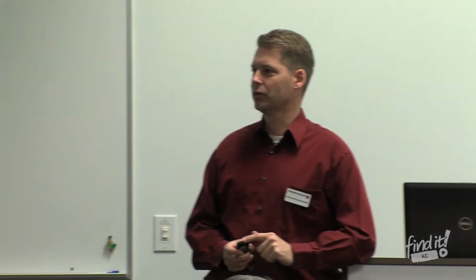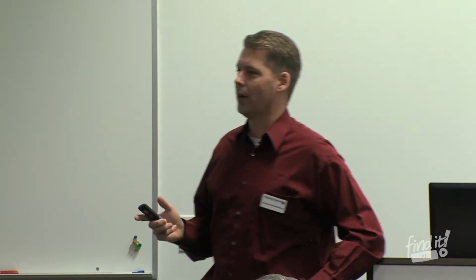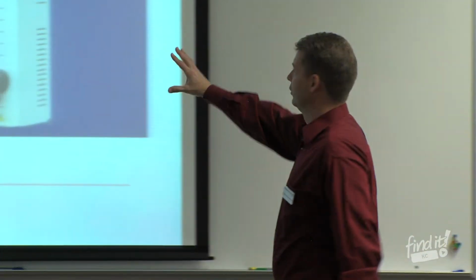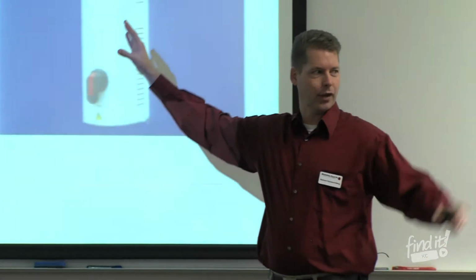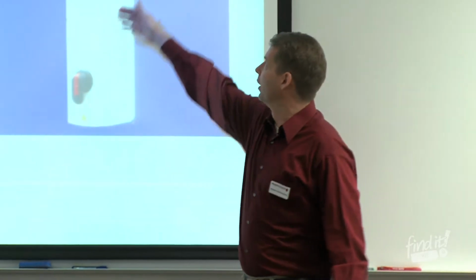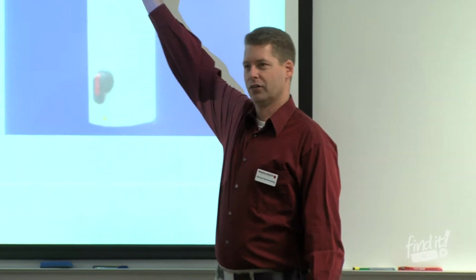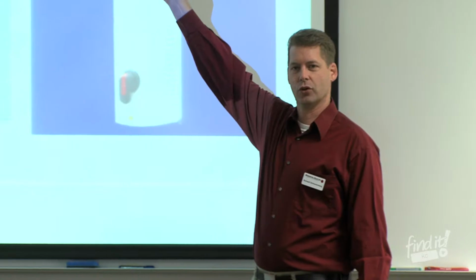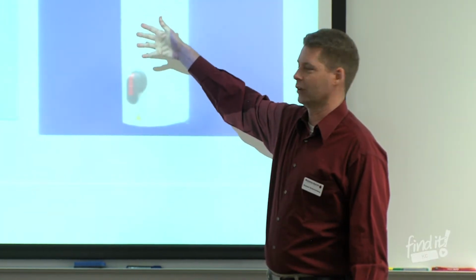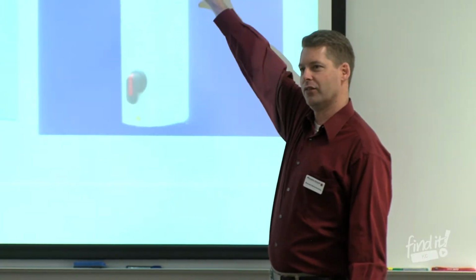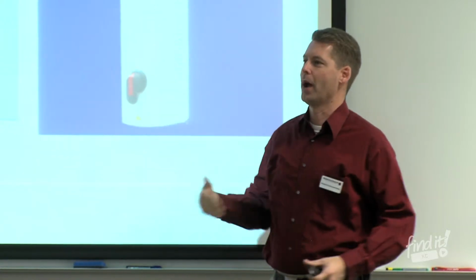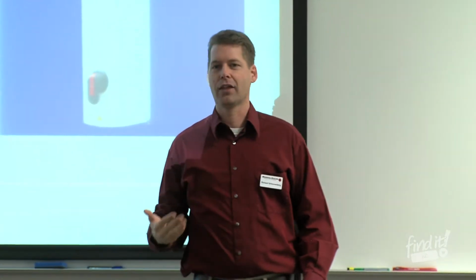Good with VFDs in general so far? Because we're going to get Paul up here next and talk about VFDs and the bypass. So I've done a simple illustration of a vertical VFD and bypass. We've got one sitting over here on the bench, but you'll notice the top portion is still just a VFD, just like those pictures I showed earlier. The bottom portion is the bypass section. So you end up with a VFD and now extra stuff on here, the bypass being the redundant path of power to the motor.